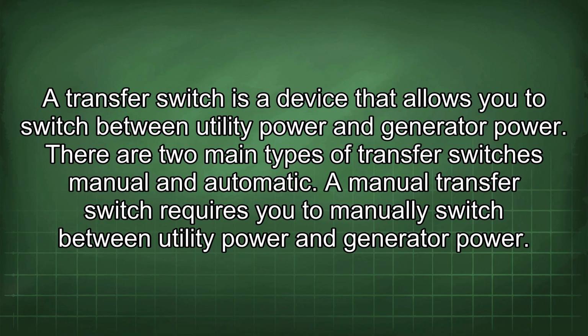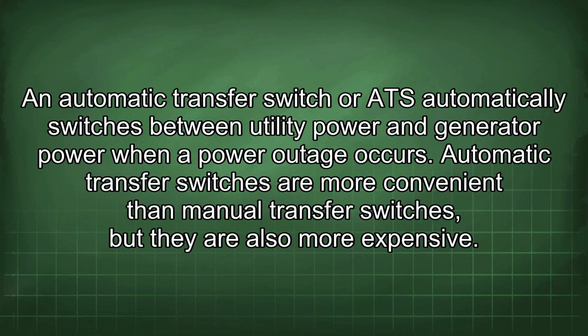A transfer switch is a device that allows you to switch between utility power and generator power. There are two main types of transfer switches: manual and automatic. A manual transfer switch requires you to manually switch between utility power and generator power. An automatic transfer switch, or ATS, automatically switches between utility power and generator power when a power outage occurs. Automatic transfer switches are more convenient than manual transfer switches, but they are also more expensive.